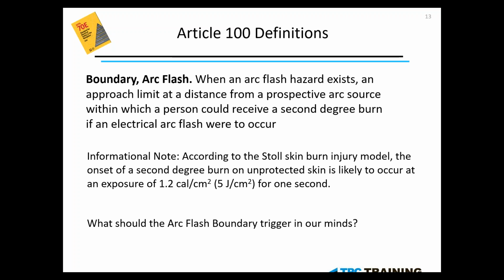This is a boundary where we will establish our barriers, non-conductive barriers. And this is typically, like I said, the outermost boundary. It is the boundary where a person could receive a 2nd-degree burn. So the intent here is to keep people out of the arc flash boundary and protect them against a 3rd-degree burn, which they will find inside that boundary. Anything outside that, hazards still apply, but it is the difference between skin cells surviving and not. And again, we'll cover that more in depth when we get into PPE next month.